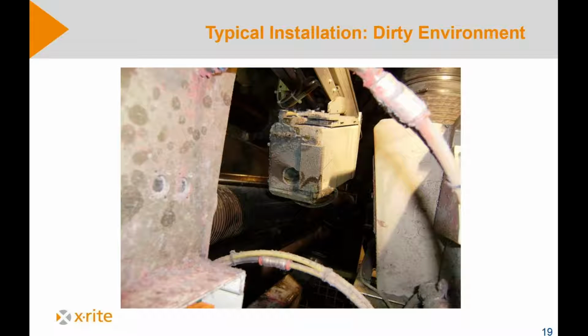So if there is no measurement, everything is closed over here. There can be no dust inside the instrument. For the measurement, we open the slit for a very short period. We have an air window over here, and we also have air connected over here, which goes from inside out. So you see everything here is protected by an airflow, so very little dust goes inside. I would say in the kraftliner process or in the kraftliner mills, you do not have to clean the instrument during production, maybe once a year when you do the service, or every calibration period, which is approximately 6 weeks. In the tissue mills, it's more often, you have to do it every 8 hours. But you see, the instrument is very clean, very stable. No problems with dust.